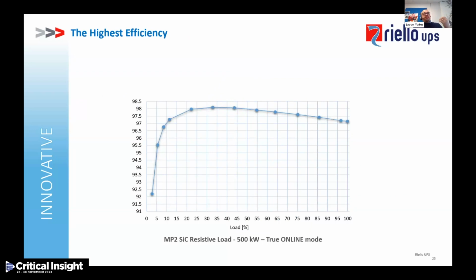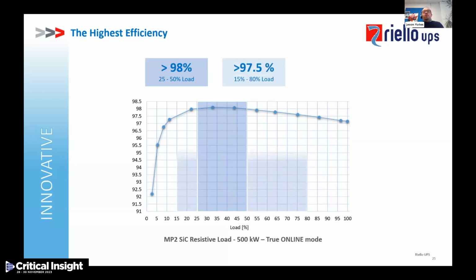If we look at the actual efficiency curve now of the devices, like all manufacturers, all will produce curves like this. We can see that between the load levels of 25 and 50% load, we are pushing an efficiency greater than 98%. So it's great for an A and a B system installation. If we widen that load level still further, you can see between 15 to 80%, we are still pushing efficiency levels of greater than 97.5%, which again, is extremely high.